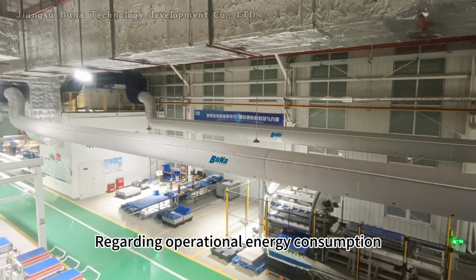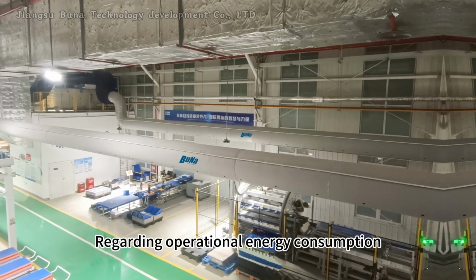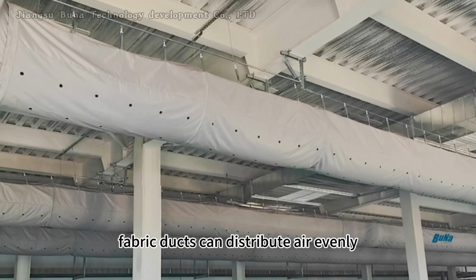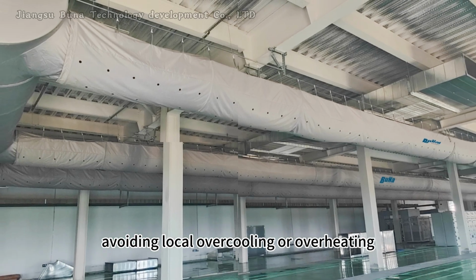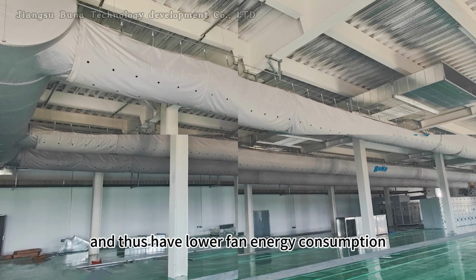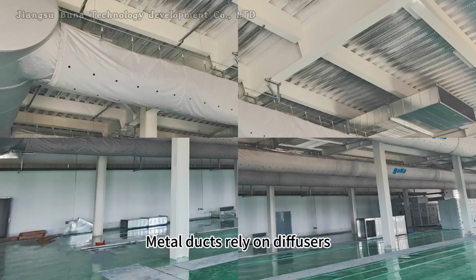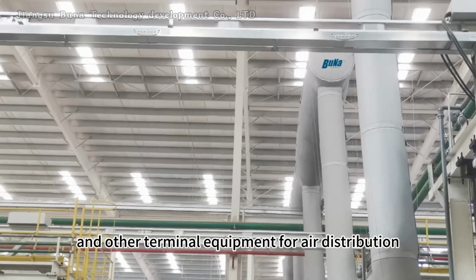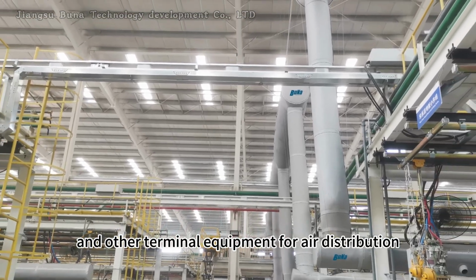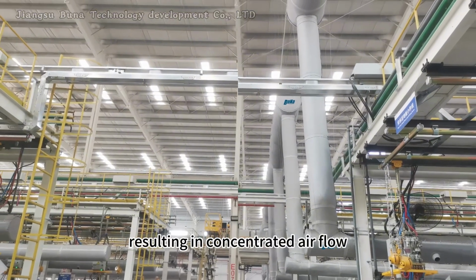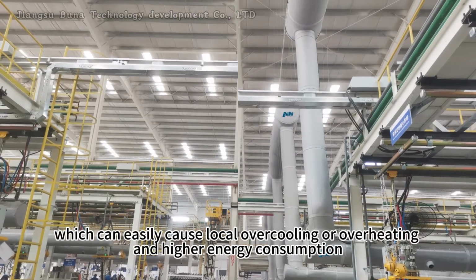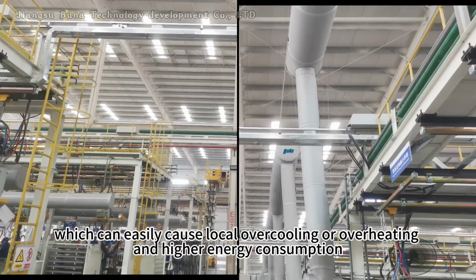more labor. Regarding operational energy consumption, fabric ducts can distribute air evenly, avoiding local overcooling or overheating, and thus have lower fan energy consumption. Metal ducts rely on diffusers, air outlets, and other terminal equipment for air distribution, resulting in concentrated airflow, which can easily cause local overcooling or overheating and higher energy consumption.